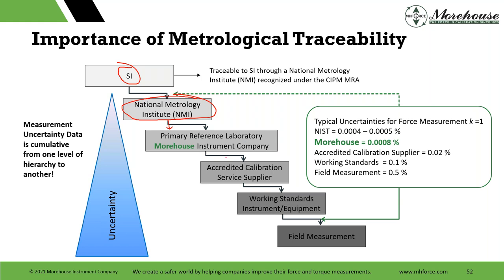And then we calibrate things for accredited suppliers' working standards, and NIST is super freaking awesome. They hit around 4 to 5 parts per million on our 120. They calibrated the weights in our 120,000 pound machine. We hit around 8 parts per million. Most accredited calibration suppliers then will hit around 0.02%, somewhere in there. This is for standard uncertainty. 0.02% or better. If they're using our cal machine, they're probably hitting better than 0.01%.